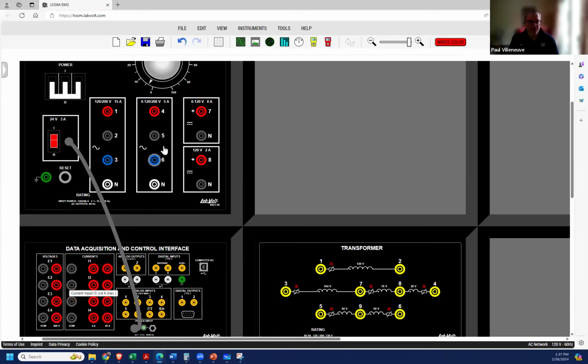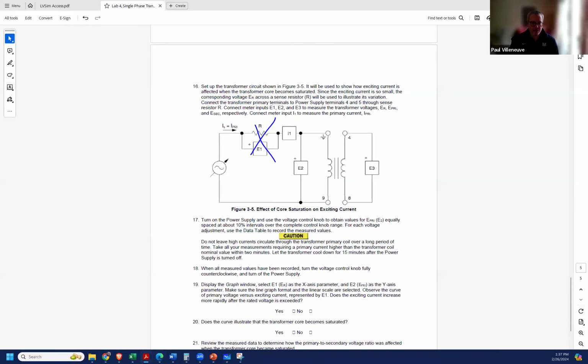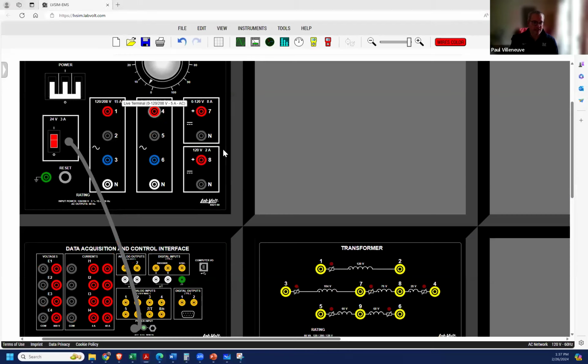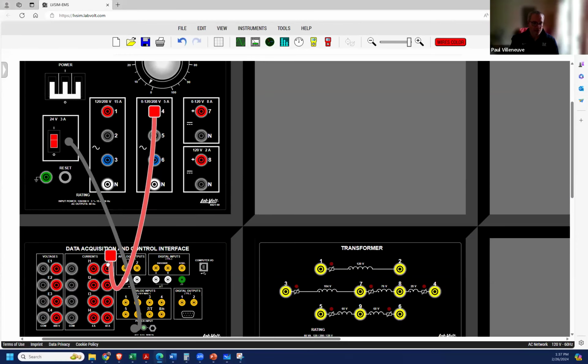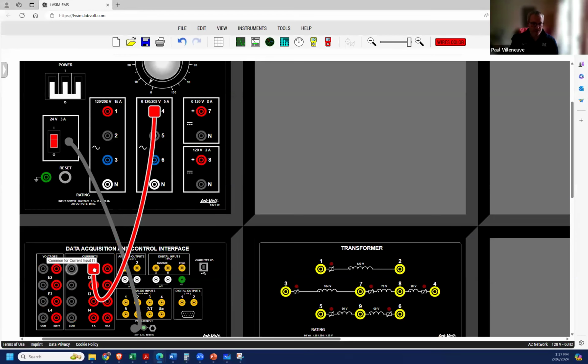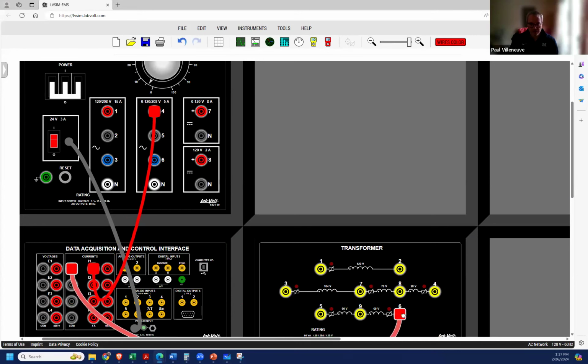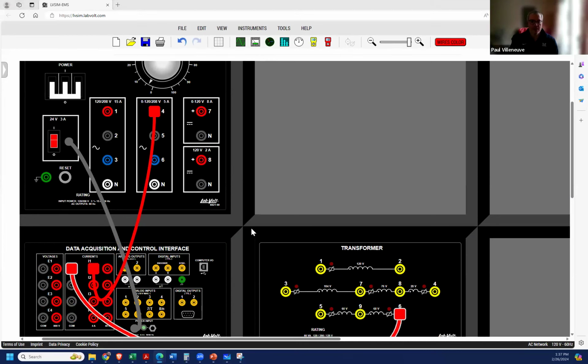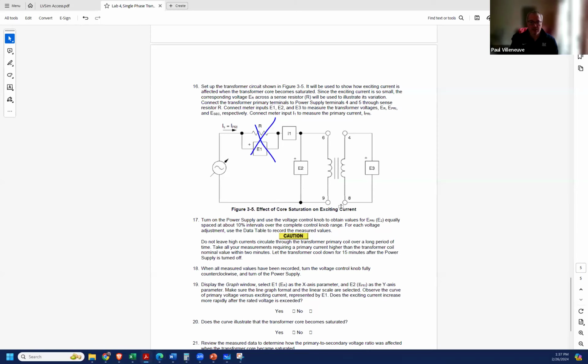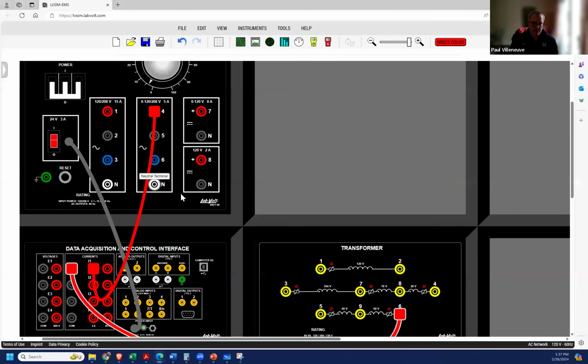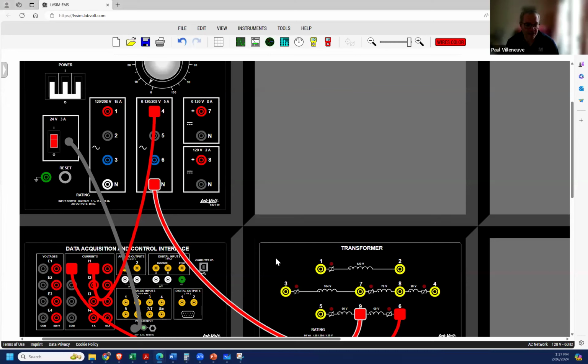First, I'm going to set up my current measurement, going from 6 to 9. So I'm measuring my current into terminal 6, and I'm going to return on terminal 9. The neutral comes here. Now I've got the ability to measure current, and I've energized the transformer through terminals 6 and 9.